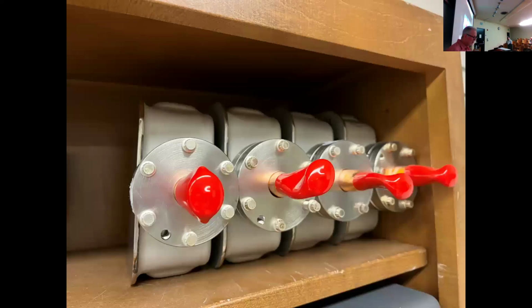And the ion column is kind of hard on ion pumps. So far, that's my collection of ion pumps, and you have to keep in mind this was in storage for more than a year. I went personally a year and a half without actually using this microscope. So I'm kind of trying to relearn things myself, but I'm sure we'll add to that. We'll add at least one more pump this year. So there are some reliability issues you can get on these.